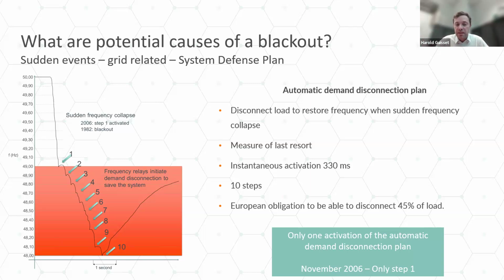At European level, we have an obligation to be able to disconnect 45% of the load at any single moment of the year. I will come back to that later because that is really a big challenge at the moment. This automatic load shedding plan was only activated once in Belgium. So again, it's very rare. That was during the system split of 2006. There we only disconnected the very first slice of the demand disconnection plan. That was enough to restore the system and to get the frequency back to 50 hertz.